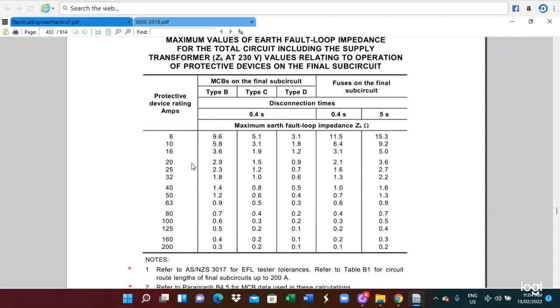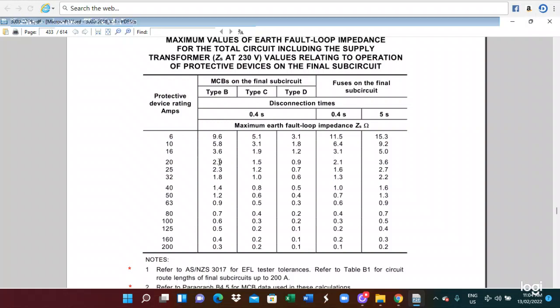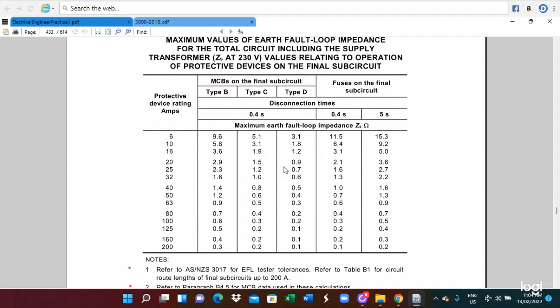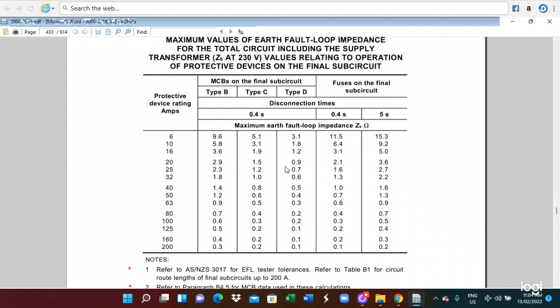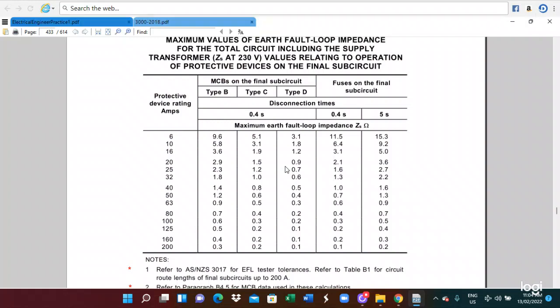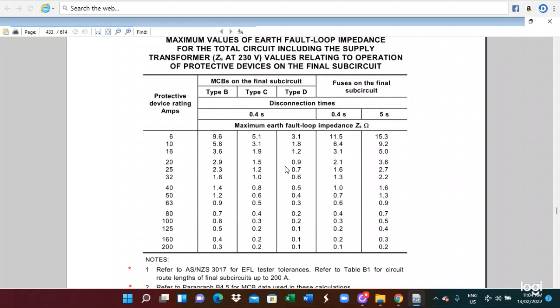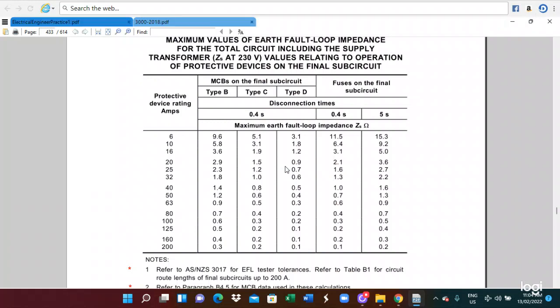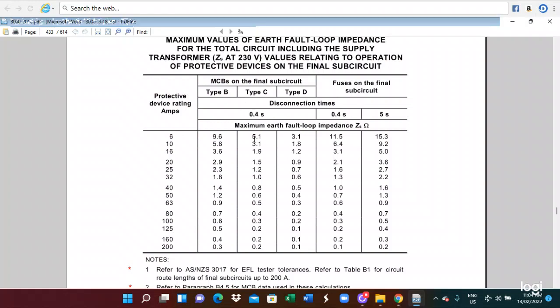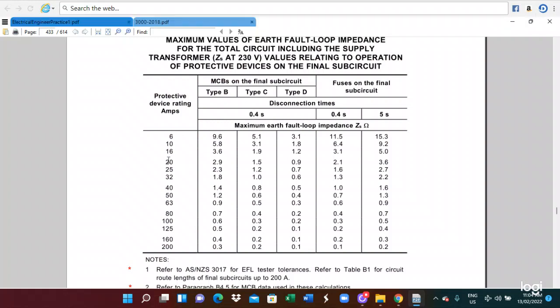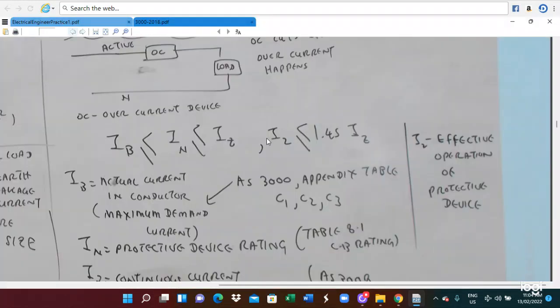This depends on the fault loop impedance. Fault loop impedance means that when an electrical fault happens, at the conductor to the fault, how much resistance is there. This is the fault loop impedance. You need to calculate the fault loop impedance. Then, depending on the kind of circuit breaker selection, you can determine the protective device rating. This is IN, the protective device rating.